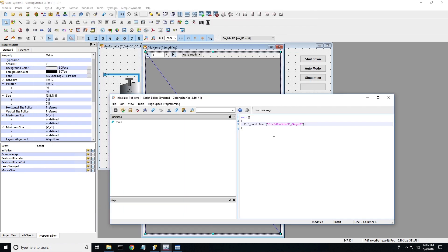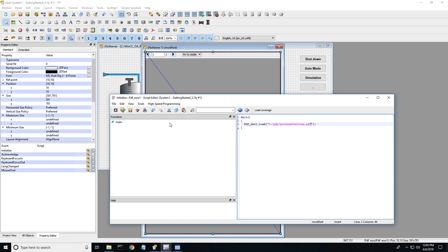With this widget, I'm going to create an initialized script because I would like it, as soon as that window opens, to run that script. I know that the PDF I just saved is in my C drive in this PDF folder and it's called process overview. Keep in mind the script editor in WinCC OA is case sensitive. Process overview, and don't forget the file extension, which is .pdf.